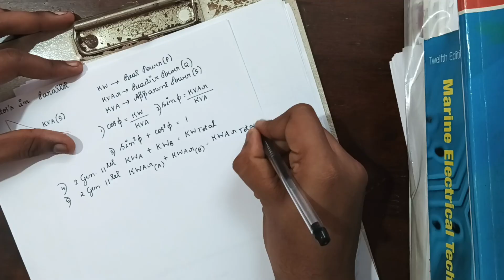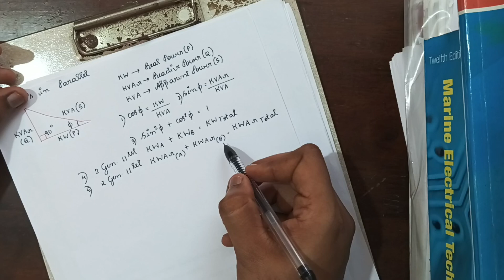Remember that the apparent power of A plus the apparent power of B is not equal to the total apparent power. Only these hold: kW A plus kW B is equal to kW total, and kVAR A plus kVAR B is equal to kVAR total. Next, let's go to the problems. These are the important formulas which are necessary.